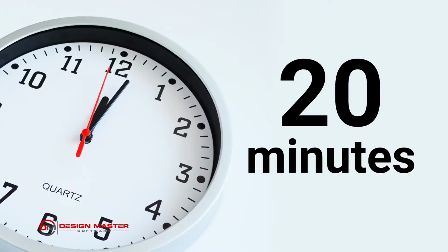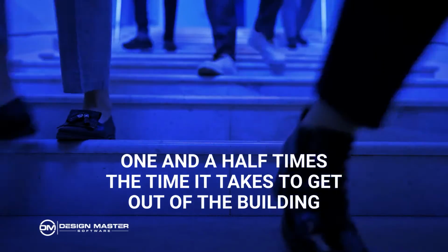The second issue is how long should it run? Fortunately, smoke control systems, unlike egress lighting, which has to be 90 minutes, only need to run for 20 minutes. The whole idea is just to be on long enough to get people out of the building. There's also some wording that it's either 20 minutes or 1.5 times the time it takes to get out of the building. So it's hard to imagine a building where it takes more than 20 minutes to get out, but I suppose that's possible. Something to keep in mind. And then I would simply size the battery for at least 30 minutes, maybe 45 minutes, and that would be sufficient.